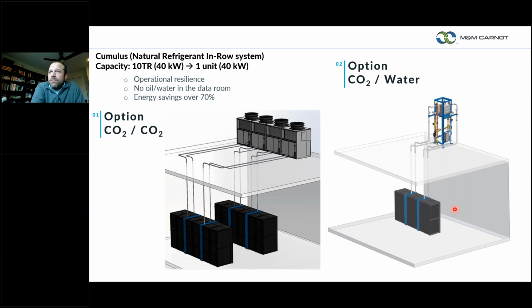One of the other asks that we had was, well, if we do have a water loop in the building, and this one happened to be chilled water, we didn't want to run chilled water to our racks. So we hooked up a heat exchanger, which is on the right, our CO2 to water heat exchanger, that will take the heat from the data center and reject it into the chilled water loop through CO2 lines going right down to that data center cooling equipment. I just wanted to show you this because I think it's important to where we want to go in the future, and basically figuring out how to move the heat from the data center into something useful. This is a nice solution for that with a CO2 to water type heat exchanger.